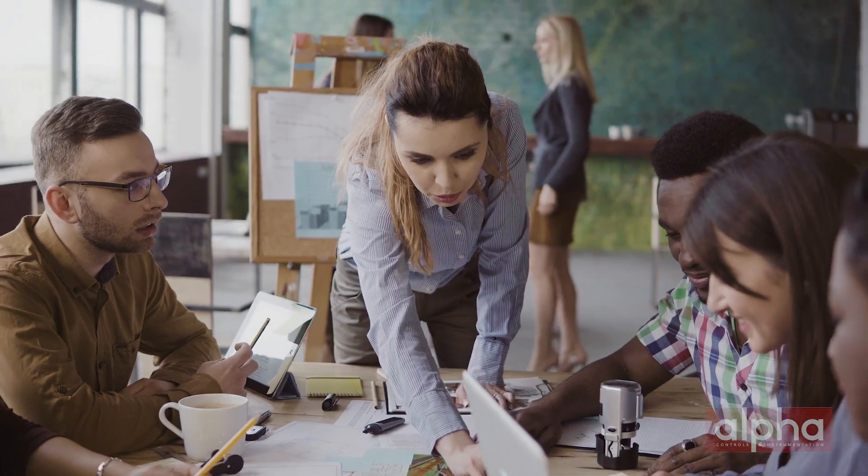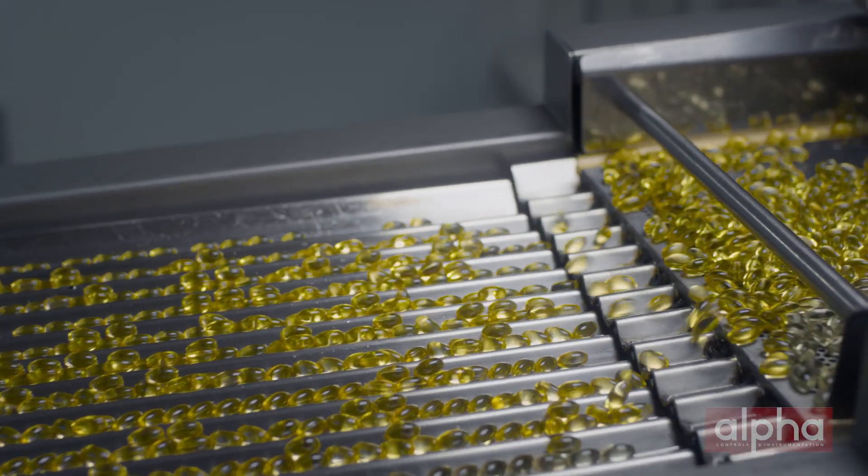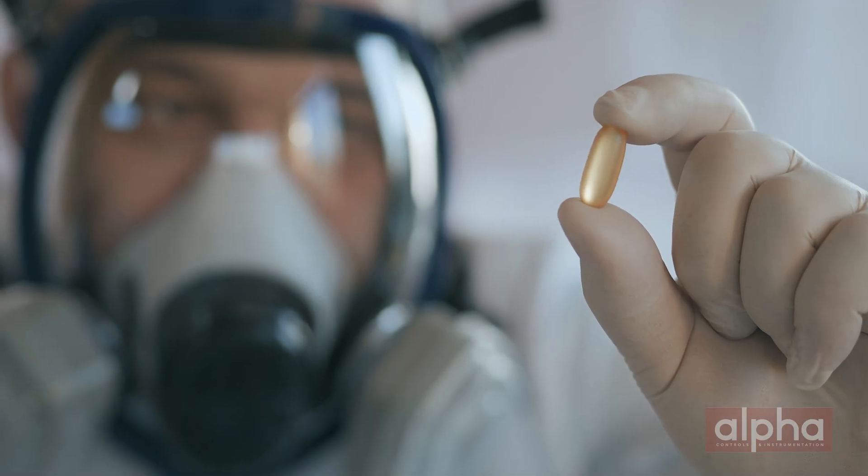Once you've got a plan, you're going to use a step-by-step protocol. This will guide you through all the specifics, such as number of loggers, where to place the loggers, and how long the run should be. The protocol is also important because it's going to be what is scrutinized by your auditors. This is why it's not just about gathering the data, but also how you report the data — so the software you're using at the end of the protocol is very important.